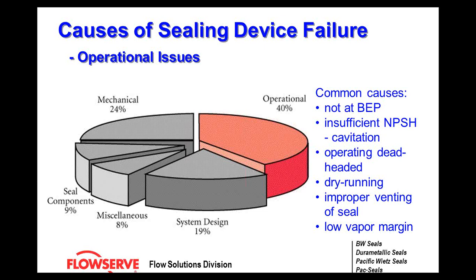One of them is insufficient net positive suction head, NPSH. This causes a phenomenon known as cavitation. Cavitation is in itself a topic for its own webinar, but know that if you don't have proper head into the pump, this will cause instability in the rotating assembly and cause a seal failure.